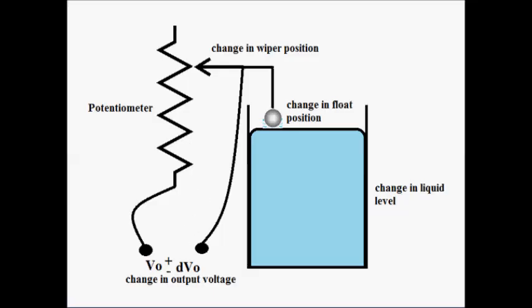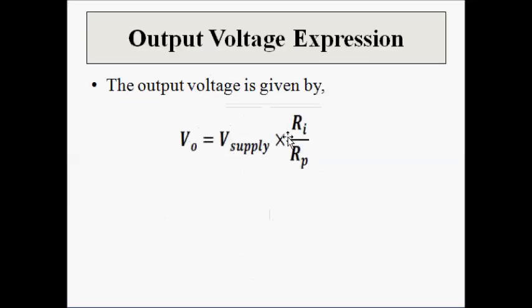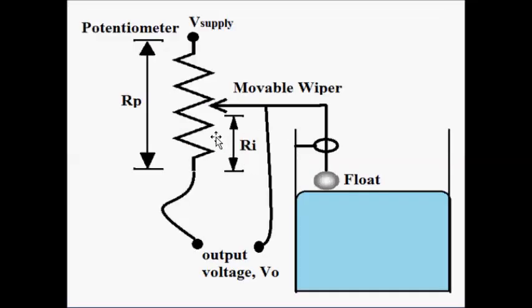The output voltage expression is determined by the voltage division rule, which we studied in the potentiometer video. The output voltage is given by: Vo = V_supply × (Ri / Rp), where Ri is the instantaneous value of the output resistance determined by the wiper position — which is directly related to the float position. So the liquid level controls the output resistance, which in turn determines the output voltage, giving a direct connection between liquid level and output voltage.